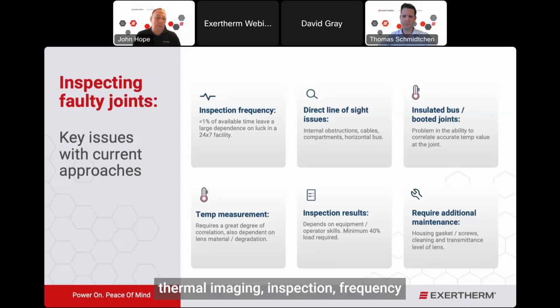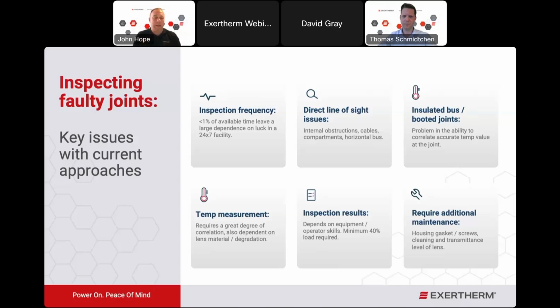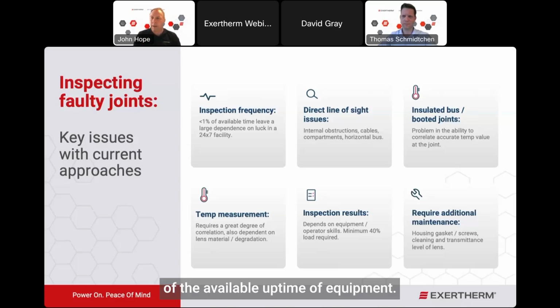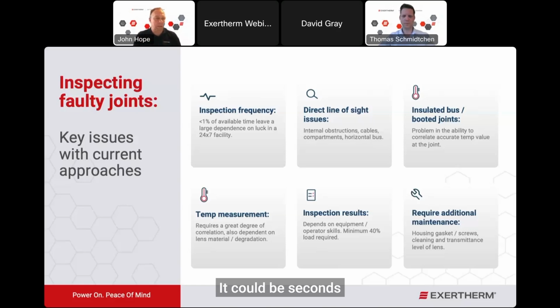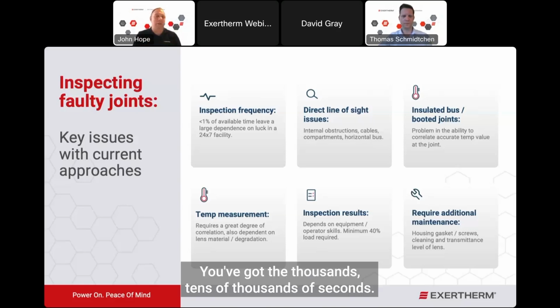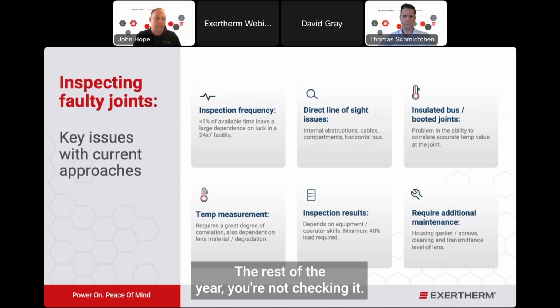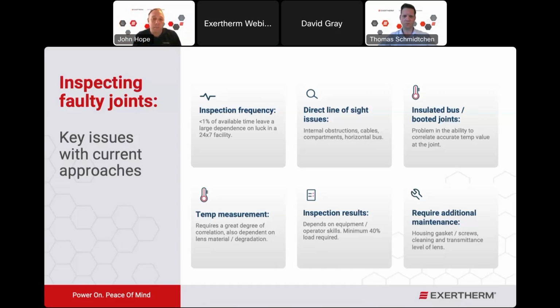Thermal imaging. Inspection frequency. It's less than 1% of the available uptime of that equipment. You're taking a snapshot. A very, very small moment in time. It could be seconds of the gear operating. You've got the other thousands, tens of thousands of seconds the rest of the year. You're not checking it.